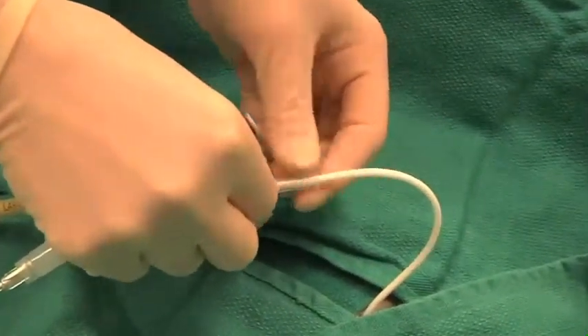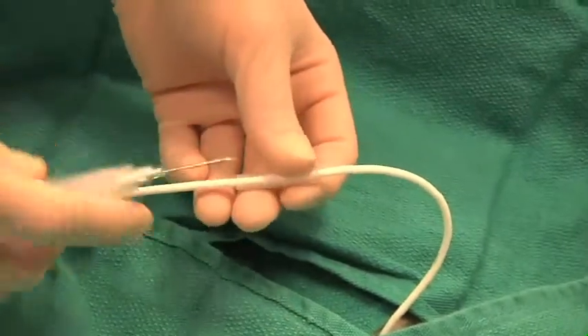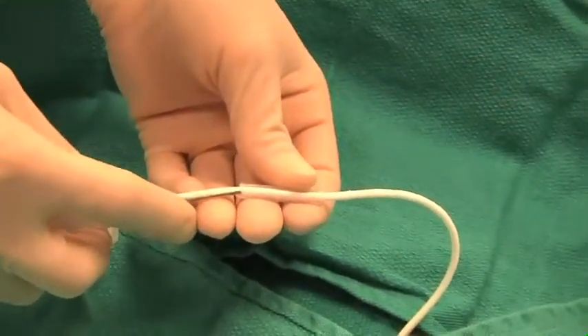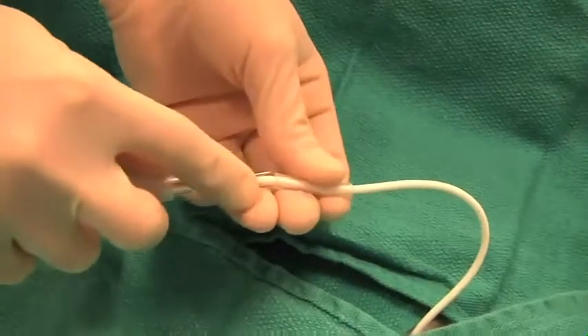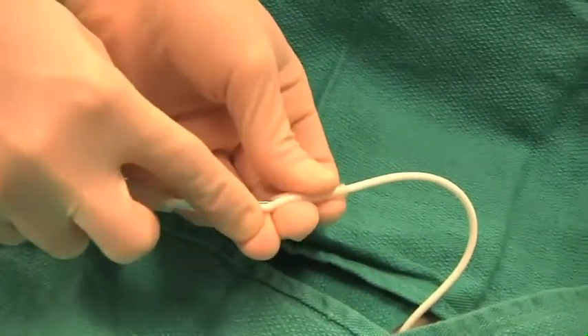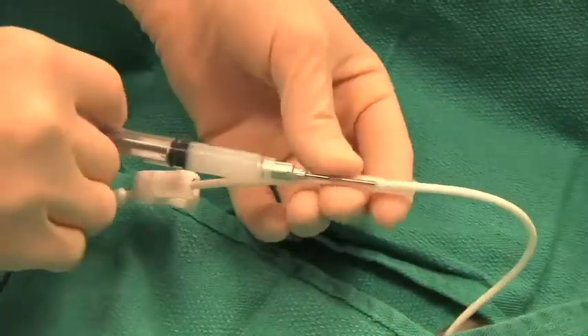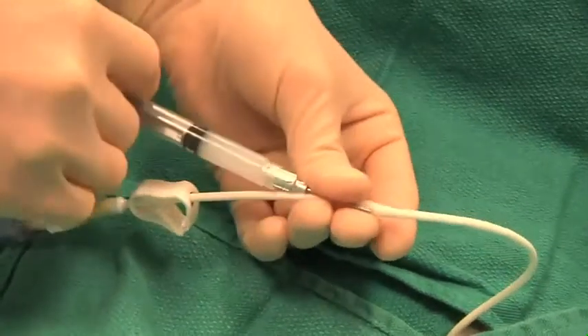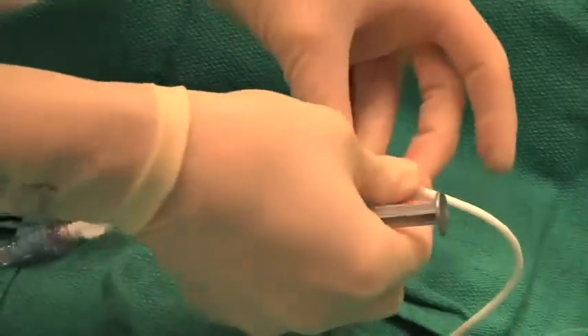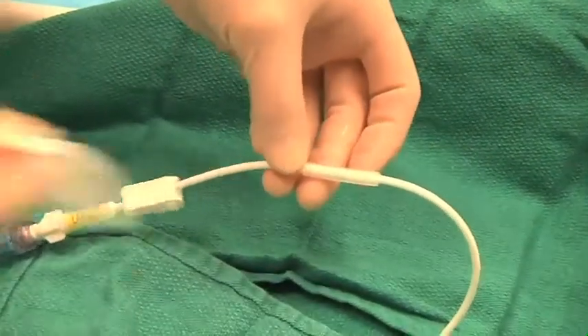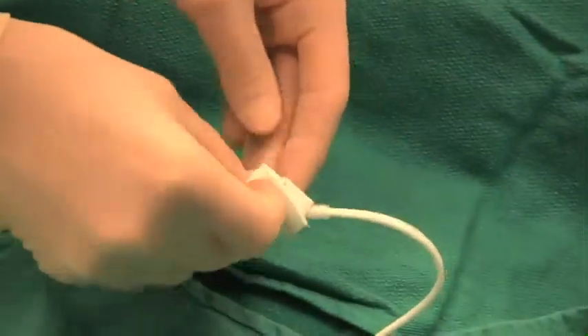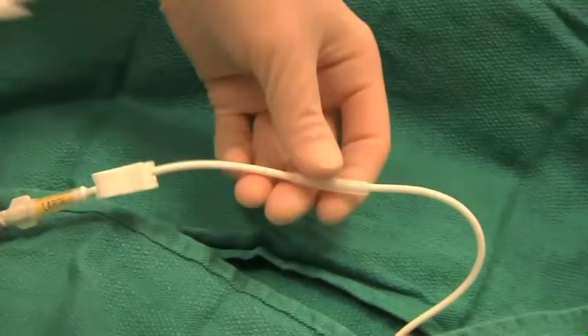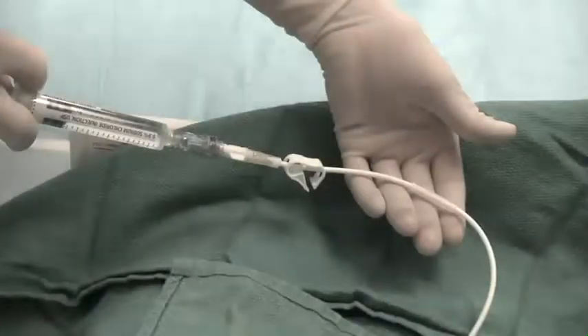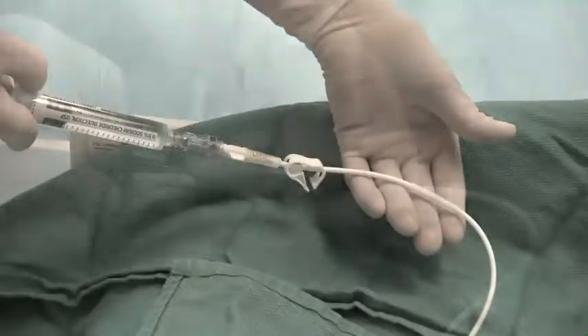Slide the sleeve over the repair area and inject more of the glue into the sleeve, being careful not to puncture the catheter. Inject enough glue until you see a small amount oozing out of either end of the sleeve. Wipe any excess glue off. If leaking is noted, make sure the joints are together and add more glue if necessary.